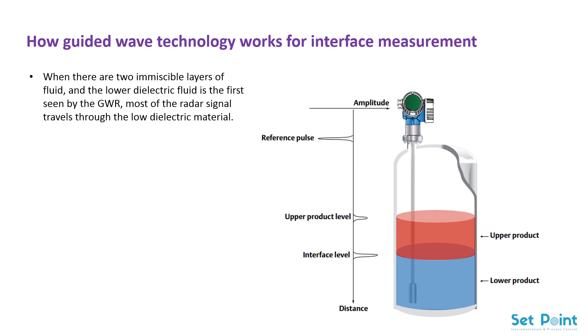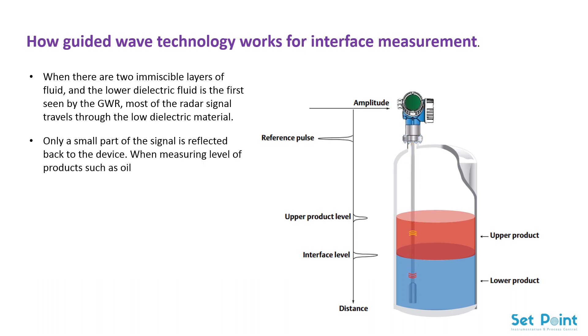When there are two immiscible layers of fluid and the lower dielectric fluid is the first seen by the guided wave radar, most of the radar signal travels through the low dielectric material. Only a small part of the signal is reflected back to the device. When measuring the level of products such as oil with a dielectric of two, less than five percent of the signal is reflected back to the transmitter.